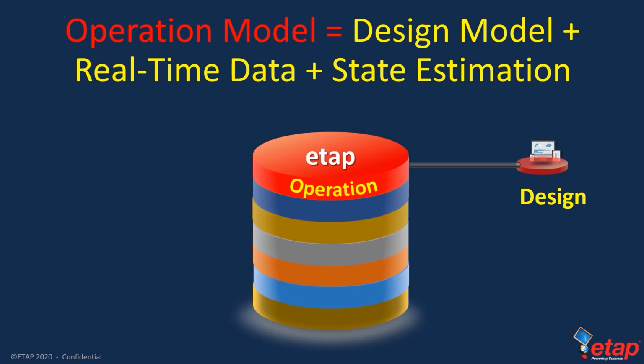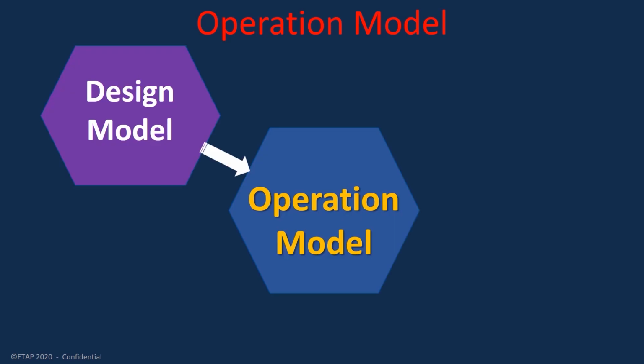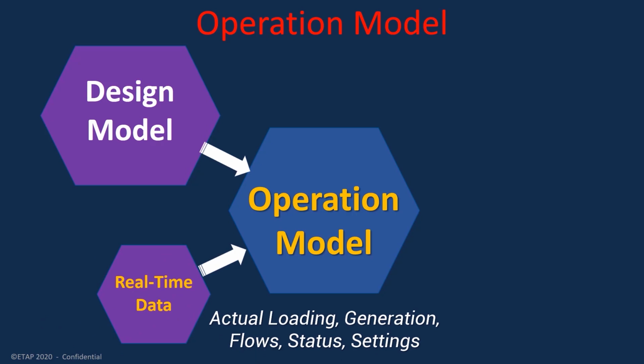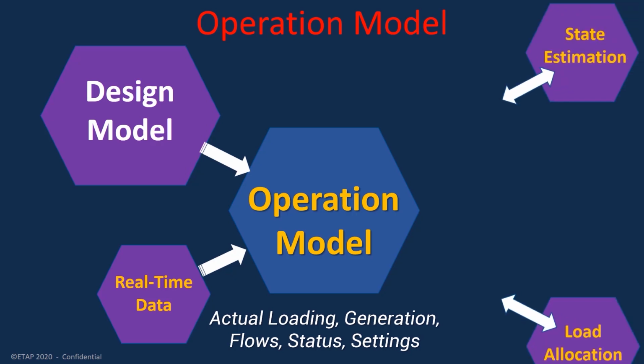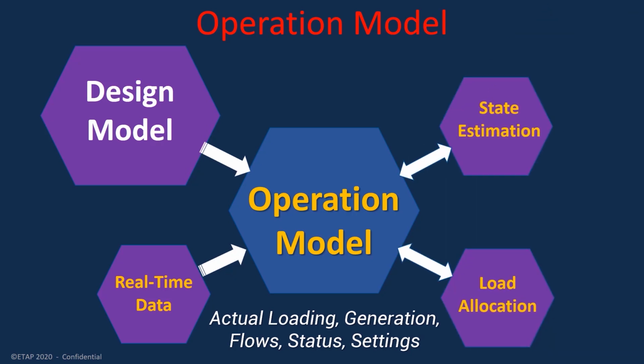However, for running the design model using actual operating values from the field, we require real-time data. The operation model makes use of the existing design plus real-time data, which is actual loading and generation values, as well as power flows and switching operating status. State estimation is built into ETAP for helping users tune the design model and provide intelligent alerts and monitoring at central locations where metering devices are not present. And when available, load allocation information.